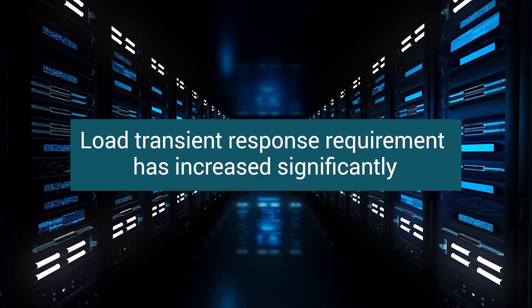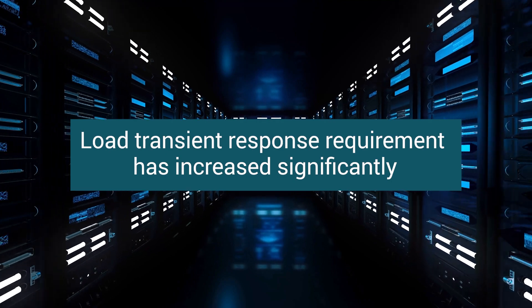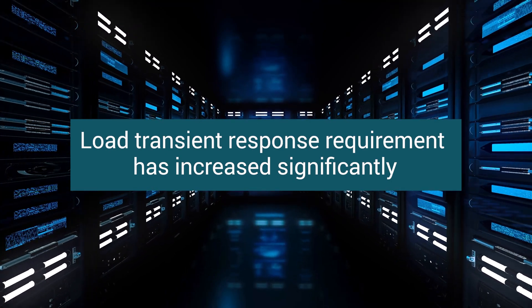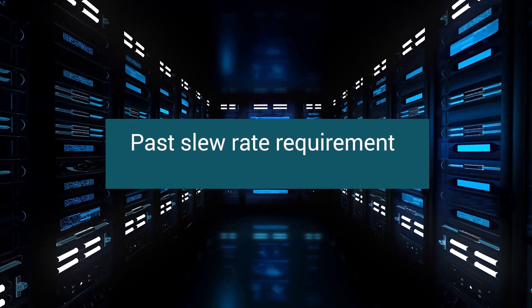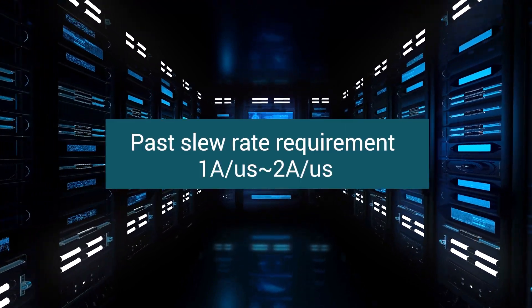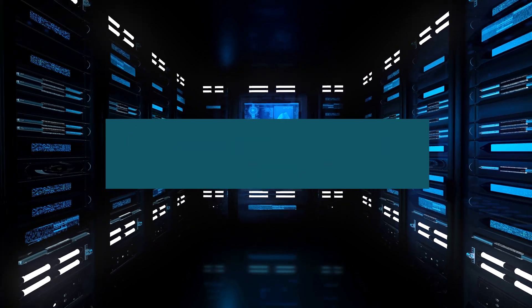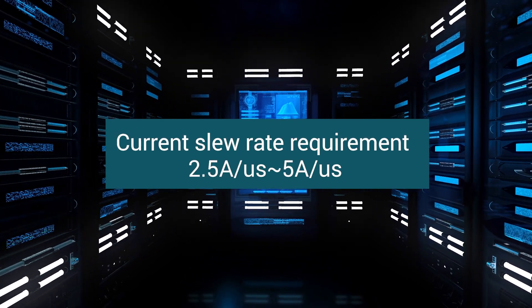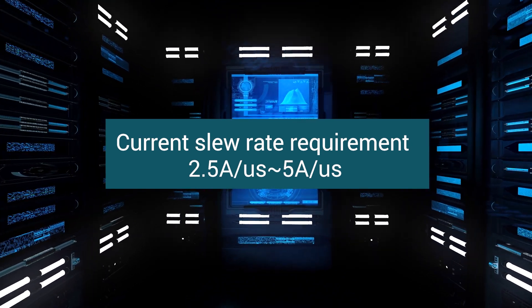Recently, the load transient response requirement has increased significantly due to higher power consumption and rapid power variation of power supply units in data center servers. In the past, the slew rate was 1 to 2 amps per microsecond. The requirement now has doubled, increasing to higher than 2.5 amps per microsecond or even 5 amps per microsecond.